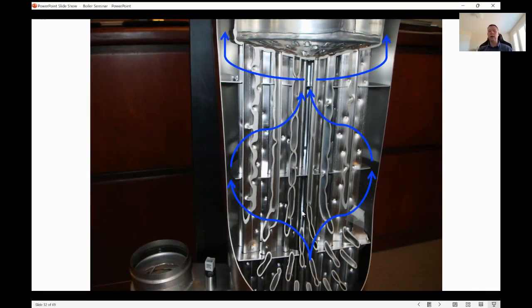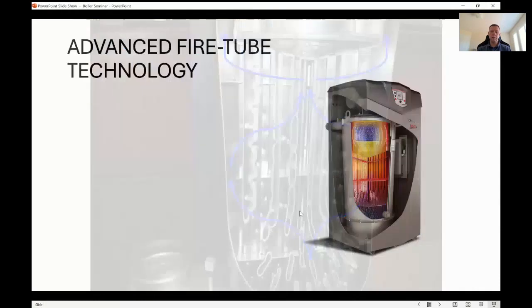On the water side too, they'll try to create as much turbulence as you can, once again, to maximize heat transfer. Now, one of the things that low mass boilers do maybe better than high mass boilers is it's a much more turbulent environment. So if you have water quality issues in your building, and there's leaks, whatever it is, a low mass boiler would probably last longer than a high mass boiler, because those tend to be designed to handle domestic water as well. They're very turbulent in there, and scale comes out of solution where things are more stagnant. The more turbulent it is, the less likely that scale precipitates out. But anyways, that's kind of a tangent there. So they do try and make it as turbulent as you can on that water side too, maximizing that heat transfer.